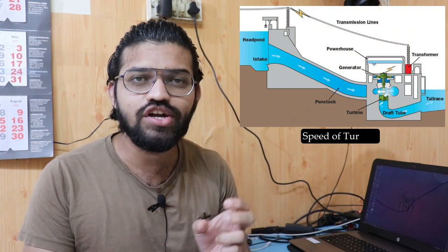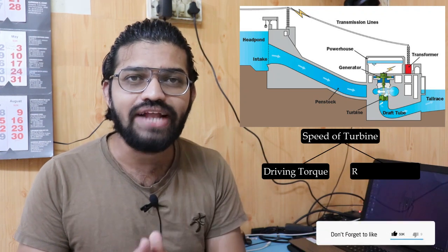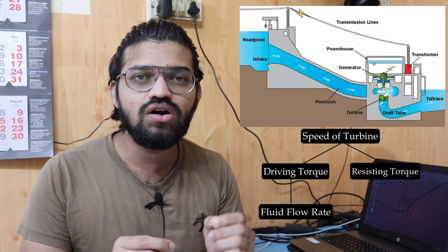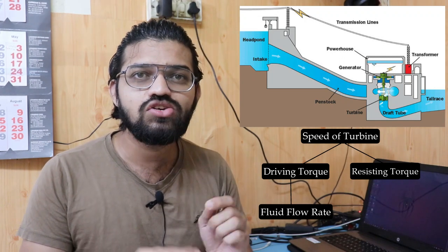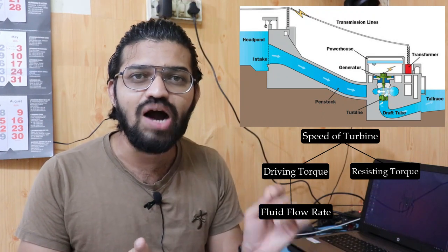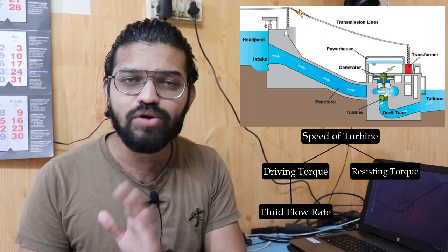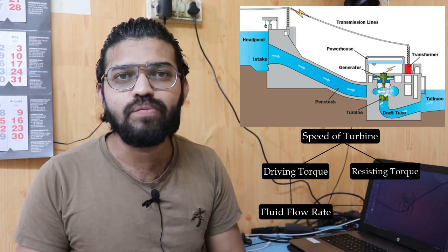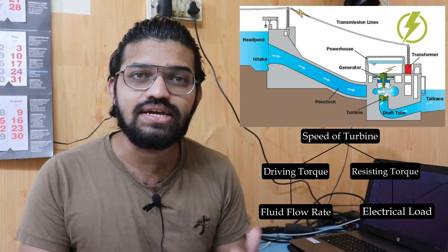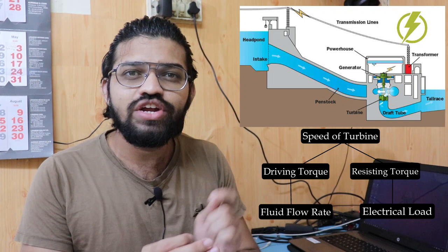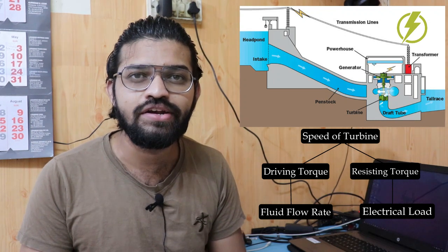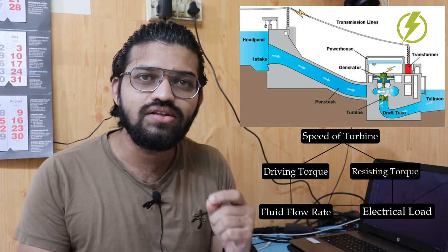The speed of the turbine depends upon two parameters: driving torque and resisting torque. The driving torque depends on the amount of fluid flowing over the buckets of the Pelton wheel or blades of the turbine. The resisting torque is the electrical load — when the electrical load increases or decreases, it affects the resisting torque. We need to balance driving torque and resisting torque to maintain a constant speed.